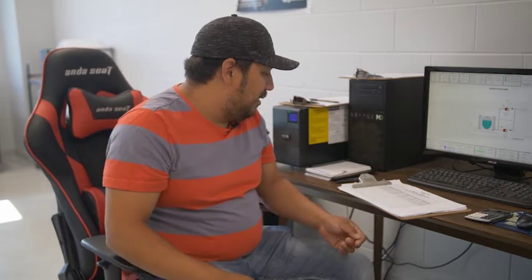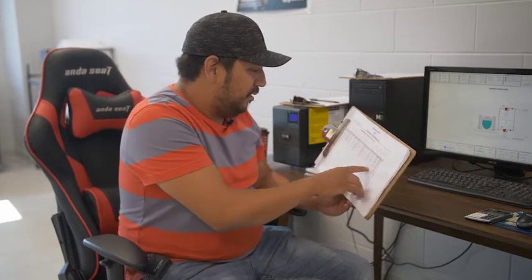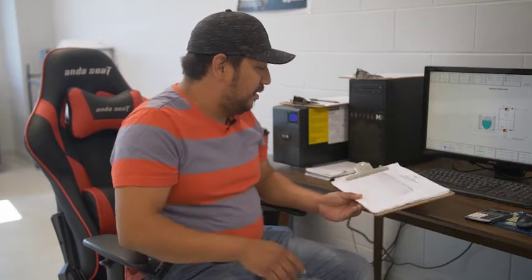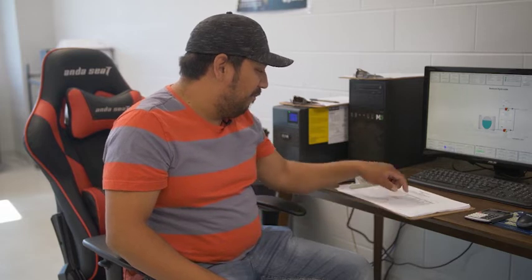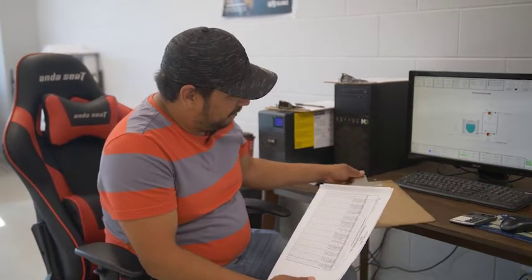With regards to anything else, like plant supply, maybe a hose was left on, or we were filling a chemical. It'd be good to track. If you look at our usage for plant supply, I can tell you what days we've actually made chemical solutions, because I know those days we're using about 200 liters, which is close to what our day tank is for a polymer, 200 liters, that sort of thing.